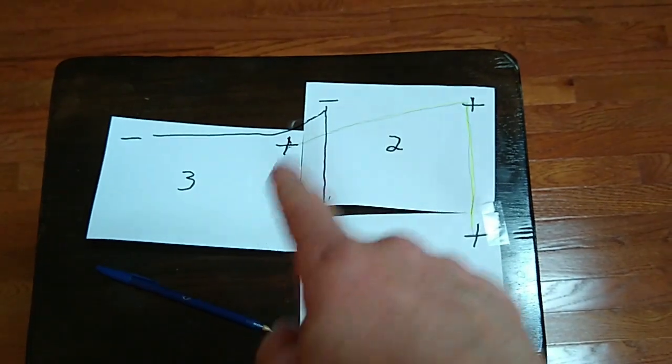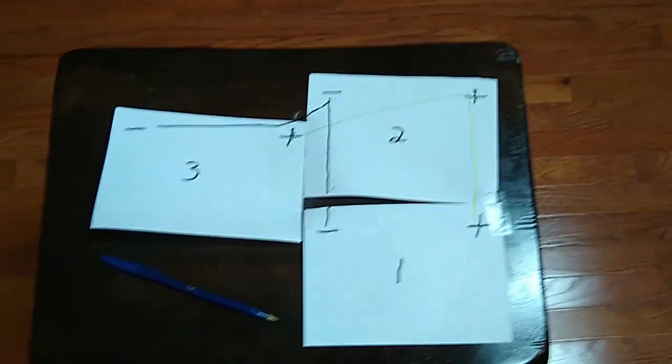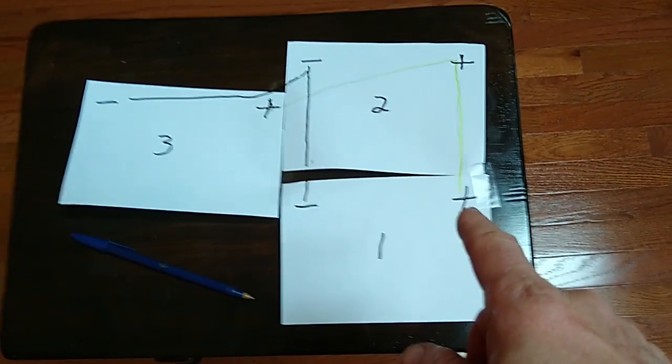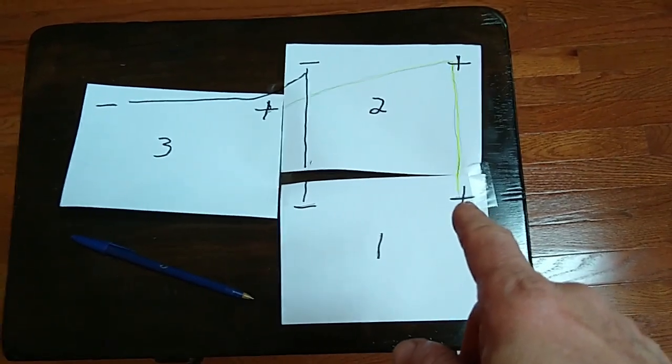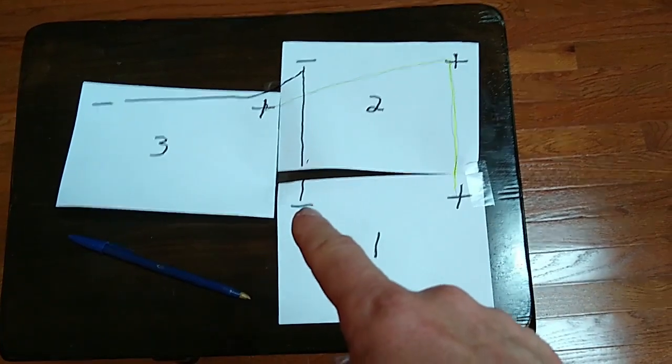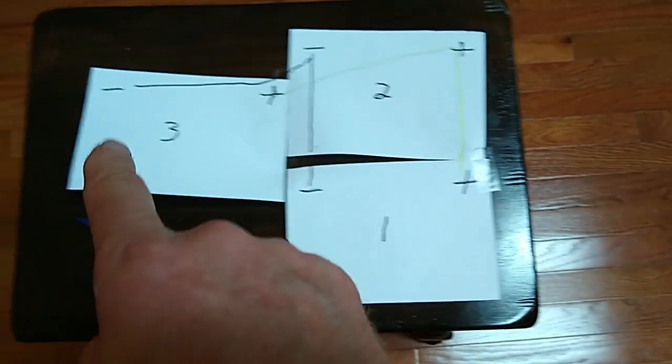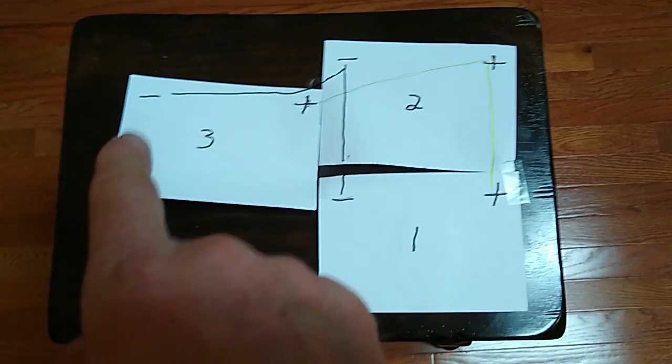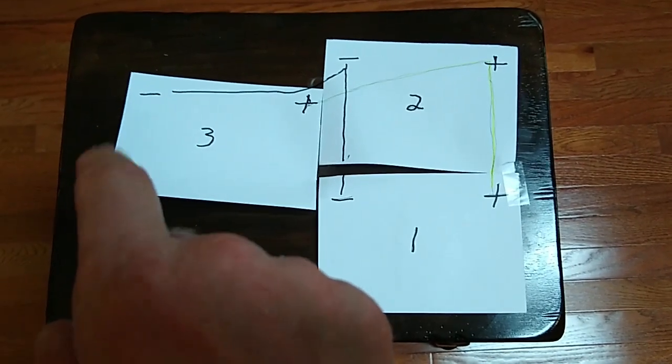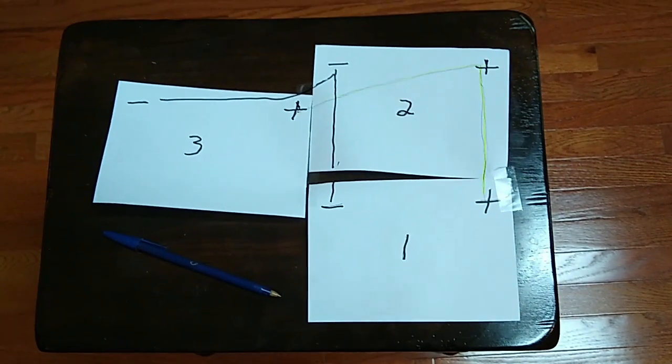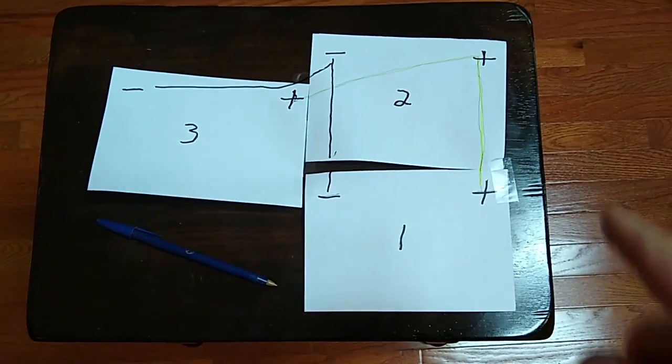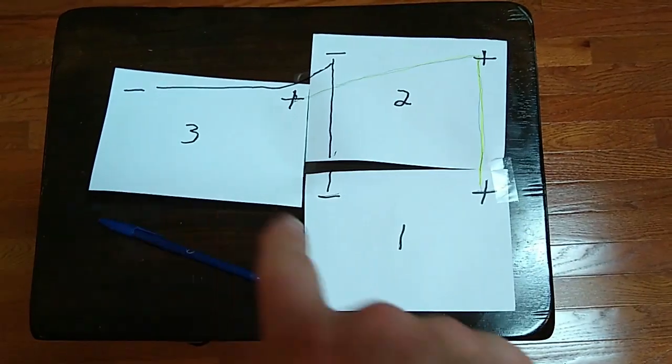Act like these others aren't even there. Okay so you're gonna bring in your positive wire from your charge controller to here and your negative wire, don't go here or here. You want to go to battery number three. You want to go here. So remember, act like there's only one positive and one negative. There's your positive on one and your negatives on three. Power in, power out.